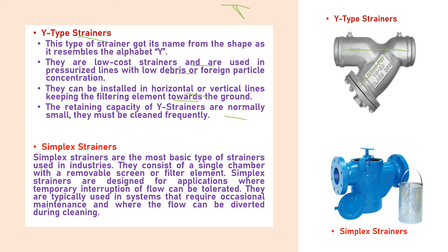The retaining capacity of Y-type strainers is small, so they must be cleaned frequently. Generally, a differential pressure transmitter is placed across these strainers. This transmitter helps indicate whether clogging is occurring in the system or strainer, so operators know when the strainer needs to be cleaned, removed, or maintained.